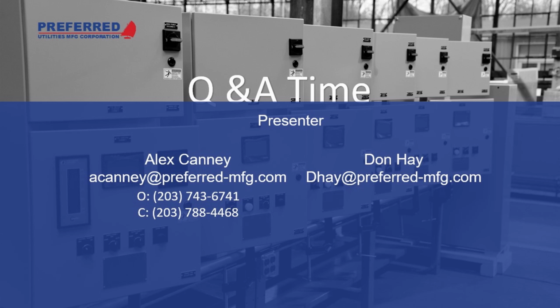As far as clean all the lines out. As far as number 4 fuel handling equipment, I've seen several systems that they've run lighter fuels in it, and it hasn't really seemed to be an issue. Is that your experience as far as the pumps and things like that? Not so much 4 oil, because basically 4 oil is just a mixture of 2 oil and 6 oil. Right. But you still have the possibility, because 6 oil is a great place to hide a lot of crud. So, and if it's not heated up constantly, you got a lot of solids that are settling. So you do, like you said, you saw the encrusted material around the bottom of the foot valve. The thing I'm trying to say is, it would behoove them to make sure that the transfer system and the storage facility is clean before they start, so they have no chance of any problems in the future.